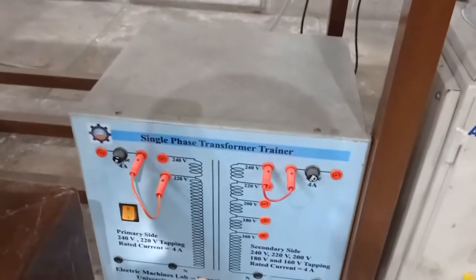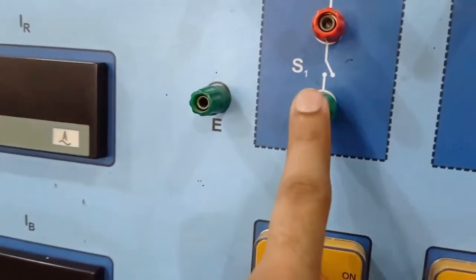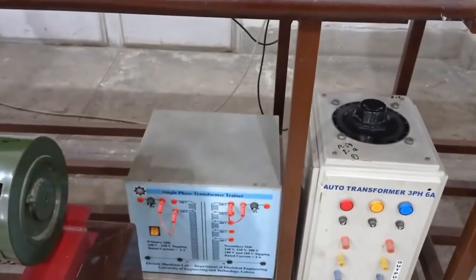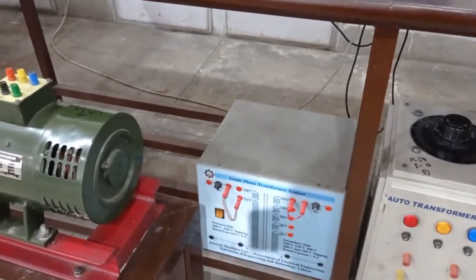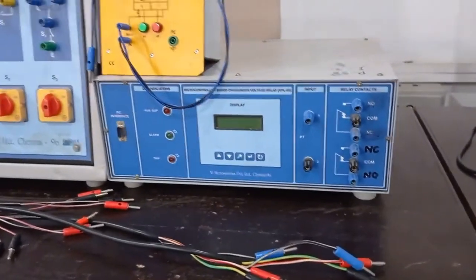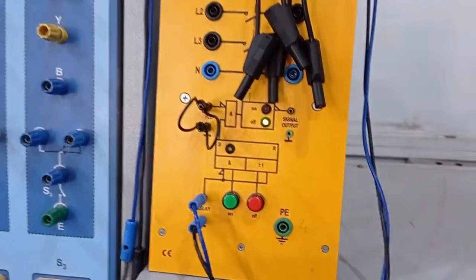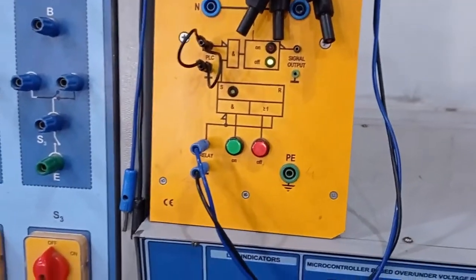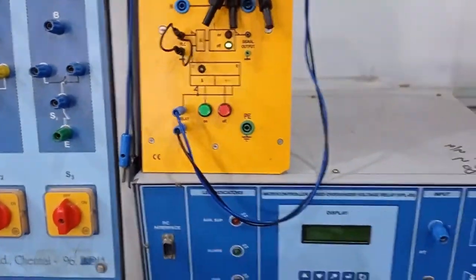So that is the neutral. Here is the transformer, and we treat this point as ground. So between this ground point and the neutral of the generator, the primary of the transformer will be inserted. On the secondary side, we insert a resistance with the help of a rheostat, and we insert our voltage relay. Our voltage relay is available here, and this voltage relay will control the operation of the circuit breaker, as mentioned in a separate video about the operation of the circuit breaker.